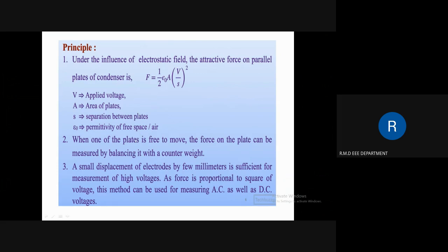When one of the plates is free to move, the force on the plate can be measured by balancing it with a counterweight. A small displacement of the electrodes of a few millimeters is sufficient for the measurement of high voltage, as the force is proportional to the square of the voltage. This method of measurement is used for both AC and DC voltages.